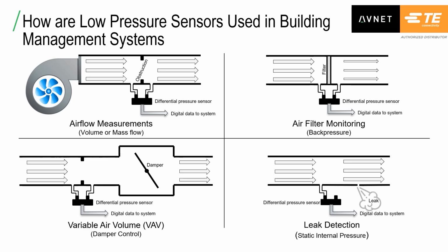The first major air-moving application for these types of pressure sensors is for airflow measurements, either volume or mass flow. It's important to understand the overall system pressure. Slight positive pressure will help keep hot air outside from penetrating into the building during the summer. Negative pressure during the winter will allow outside air into the building to maintain humidity. Control of the air pressure inside the building is key to maintaining and keeping the building comfortable.